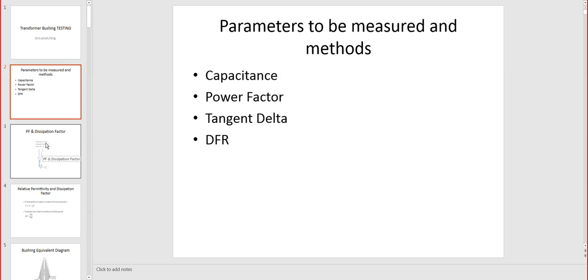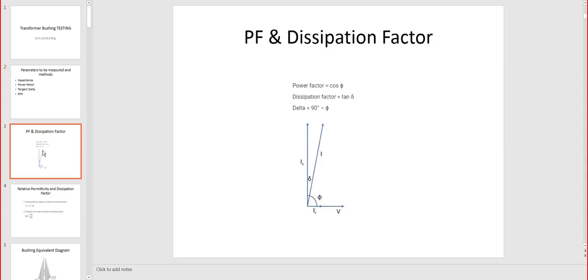So what's the purpose of this testing? It is to prove the integrity of the bushing, as far as there is no major leakage current, no internal damage, no external damage, no chipping on the skirts of the bushing, because that can lead to discharge. We know all this ends up in a bolted fault and damage that is more major than can be stopped before it is actually happening. So of course, when we reinstall bushings, replace bushings, or install a completely new transformer, this is part of the testing.